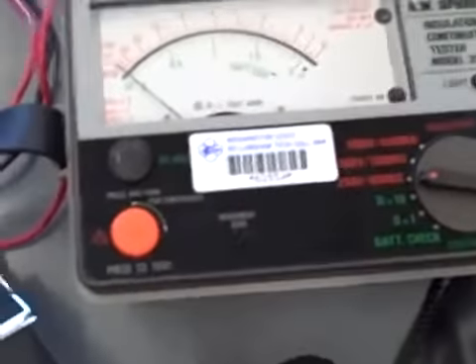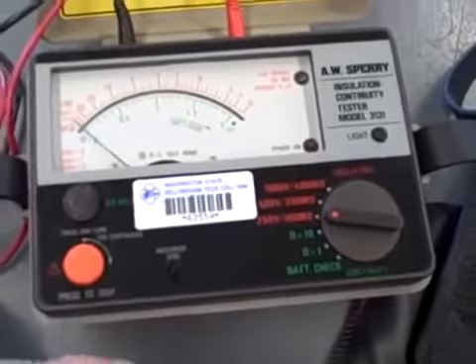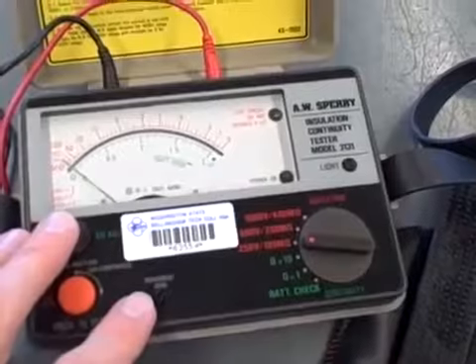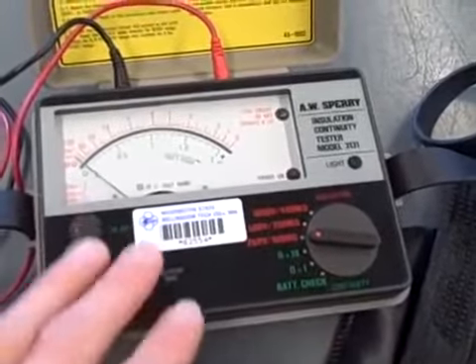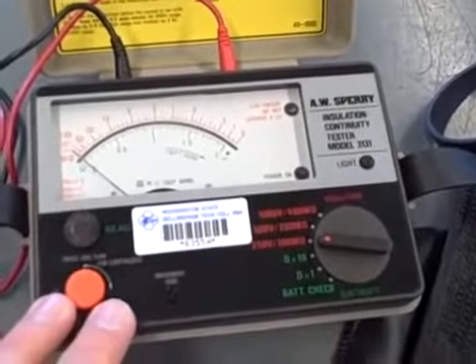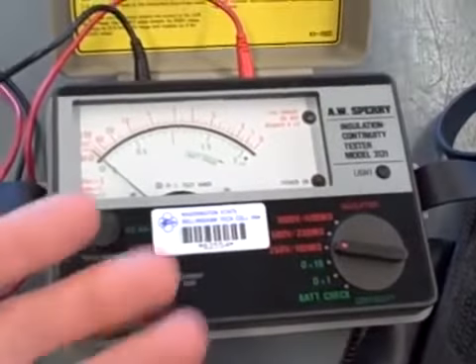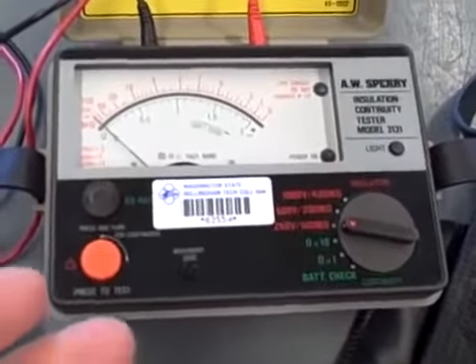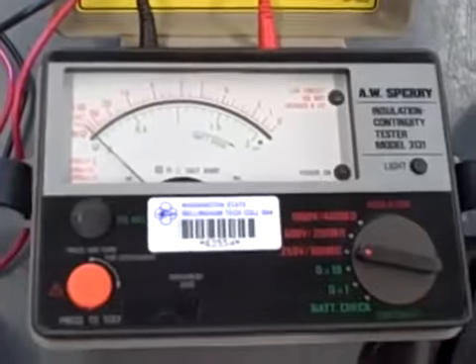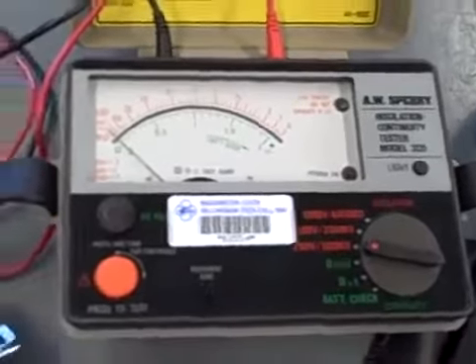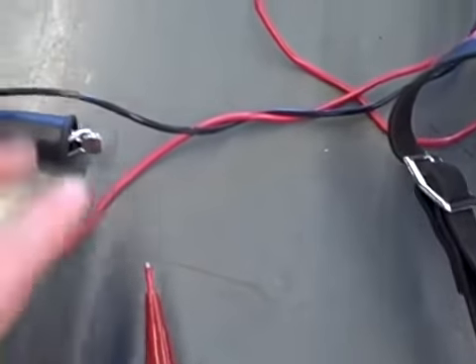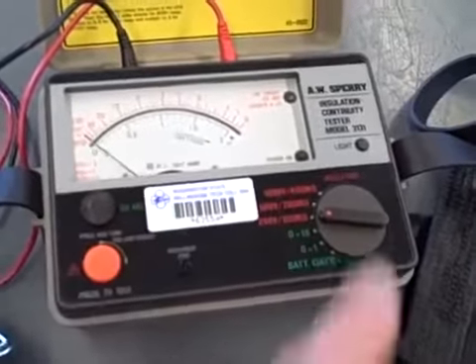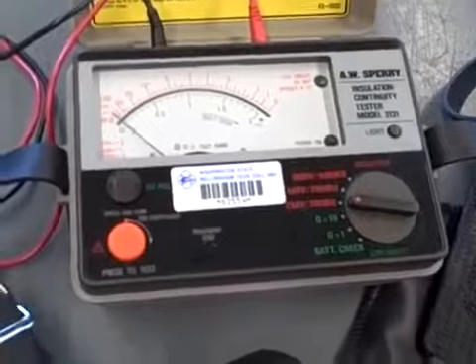I have seen electricians destroy VFDs by connecting the output of a megger to one of the terminals, T1, T2, or T3 on the variable frequency drive, and then applying high voltage with the drive off. What they were trying to do is test the motor that the drive was connected to, but in applying this high voltage between one of the motor terminals and ground, they were simultaneously applying a very high voltage to the switching transistors of the variable frequency drive.